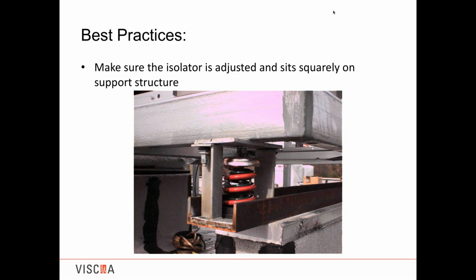But coincidentally on this one, there was also an issue with the support structure underneath, and it was improperly spaced, and that's why I mentioned it's very important to get all of the dimensional information for the equipment before you lay down your support structure. The contractor had to add a separate piece of steel, in this case a channel, to support the isolator. That channel, if not sized right, can also become a spring and can deflect under load, and that will destroy your isolation system. So other than this picture showing the top plate touching, it's showing a misaligned support structure.